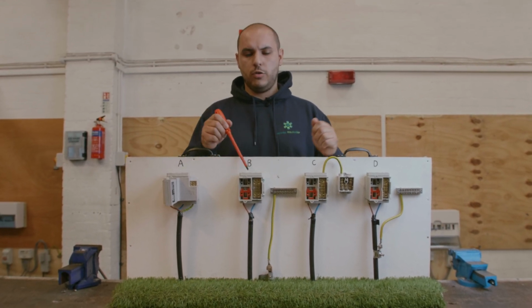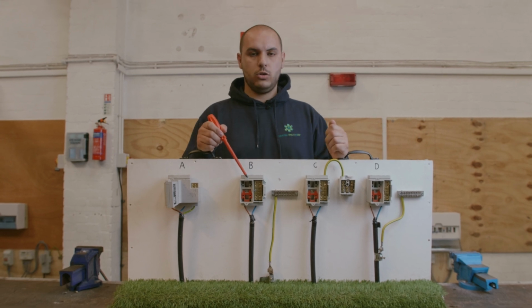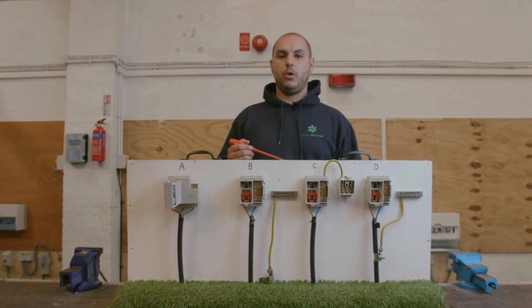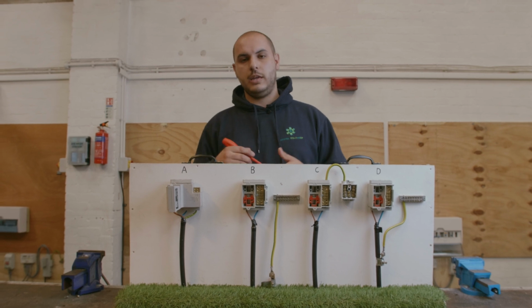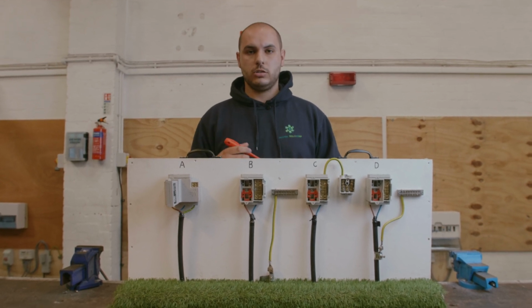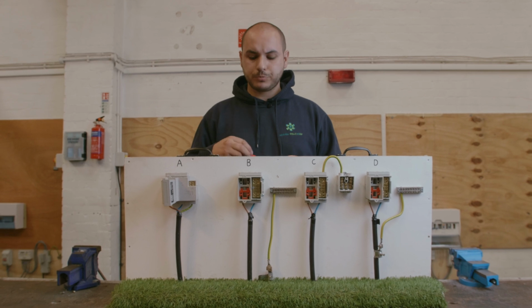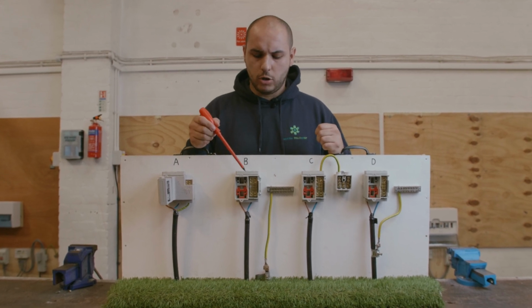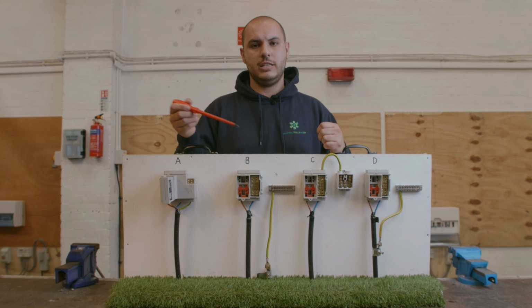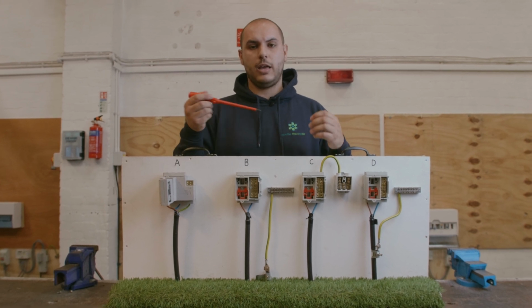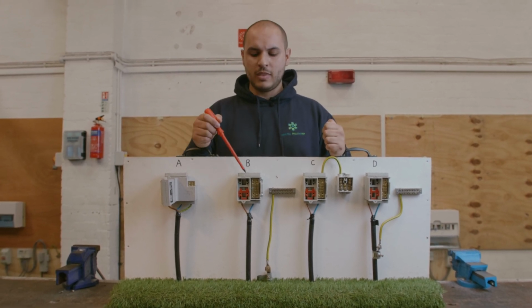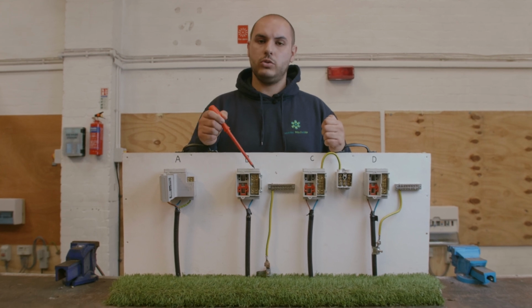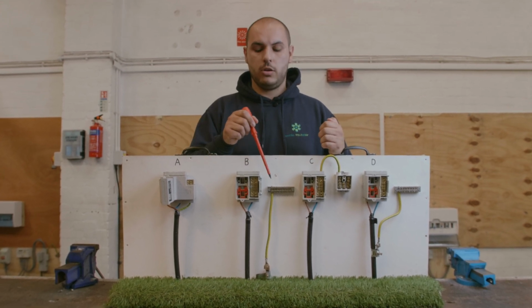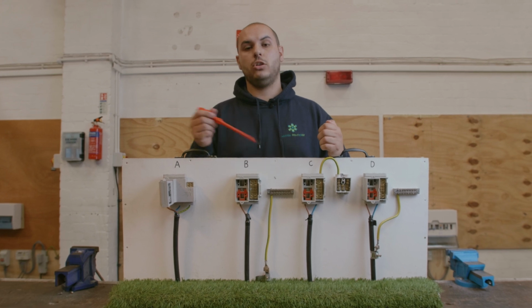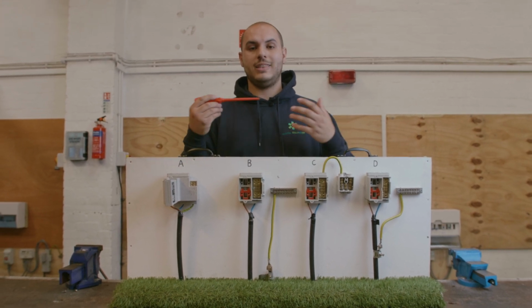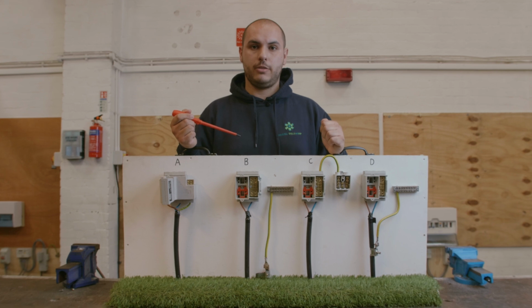separate. Just another point on the TT system, the DNO doesn't have to provide a main earth to the property. So for example, in places such as rural locations, that kind of stuff, or where there's overhead lines coming in, they may be adopting a TT there. So what would happen is the DNO would put in the supply, they'd supply the property with both line and neutral, and then the customer or the client would get an electrician in to come and earth the installation by installing an earth electrode and using that as the earth fault loop path.